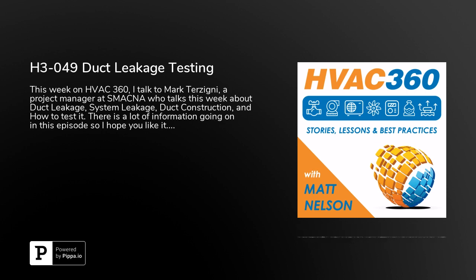I would say it only makes sense now to basically flat spec seal class A on almost all ductwork. It doesn't really add that much cost. In fact, most contractors will tell you it's certainly worth the effort to put the sealant on duct, even on the low pressure side, just because it does reduce the leakage. And that's really what's becoming the norm. A lot of contractors do it anyway, whether it's specified or not. But even if they didn't, you're seeing, for instance, ASHRAE 90.1 starting to require seal class A. Even the base mechanical codes are migrating. They're not quite there yet, but they're migrating to seal class A. And that's something that SMACNA is in support of. It certainly makes sense to seal the ductwork, high and low pressure, if you will.